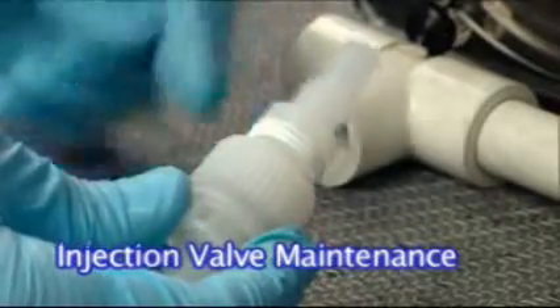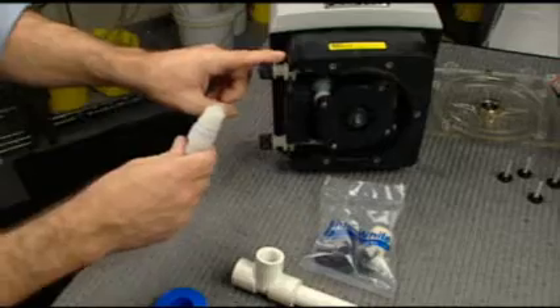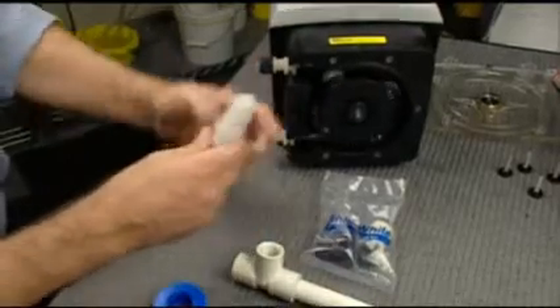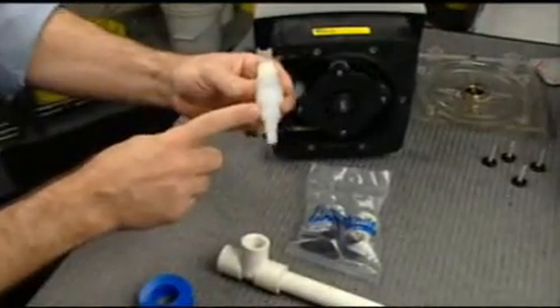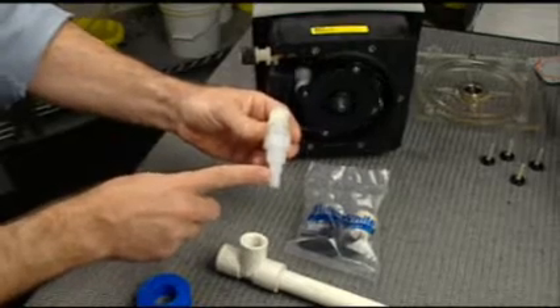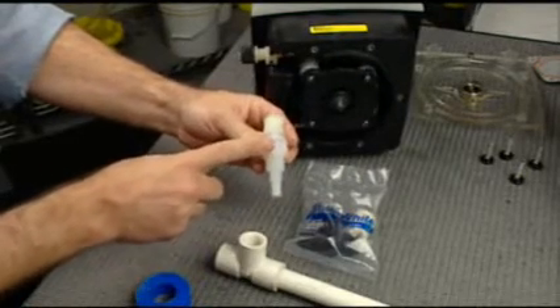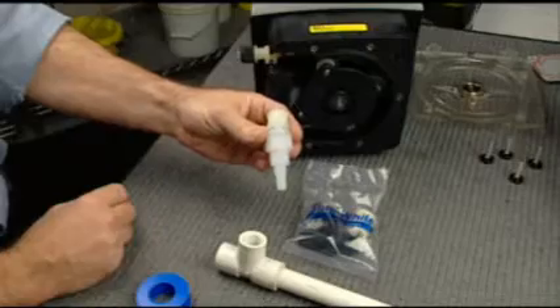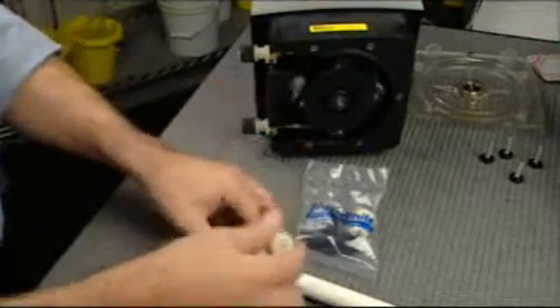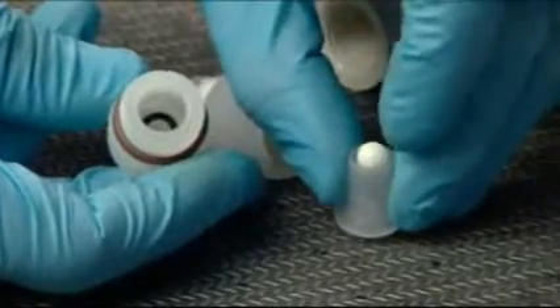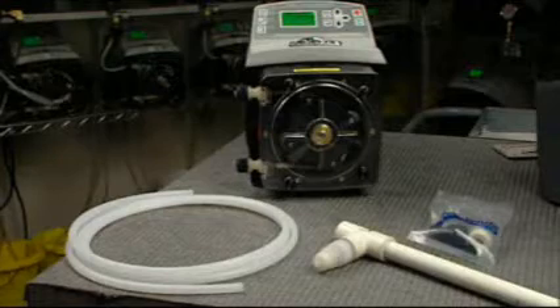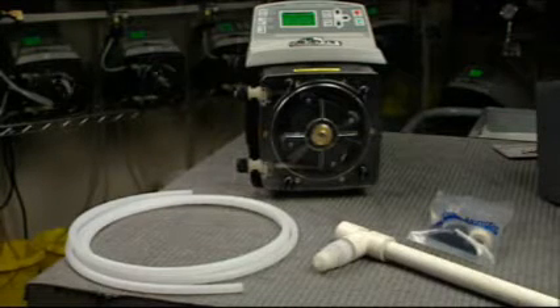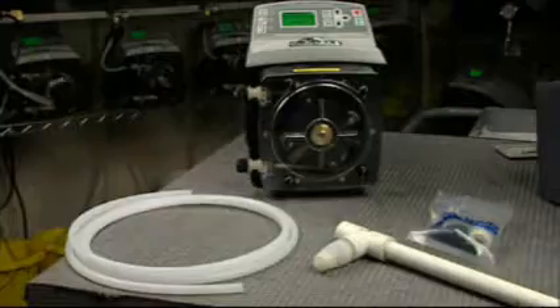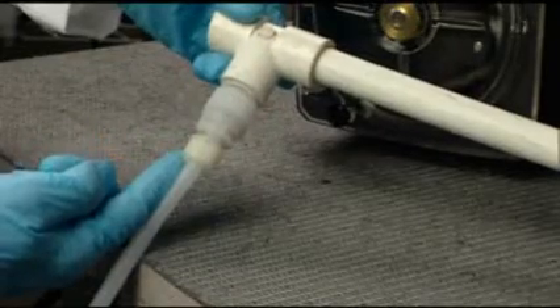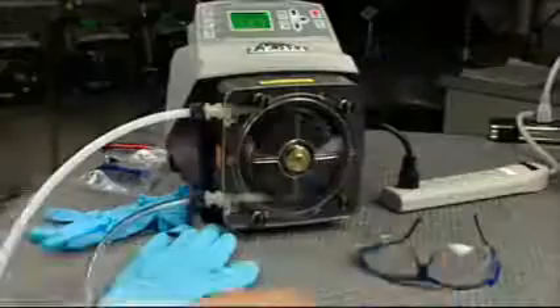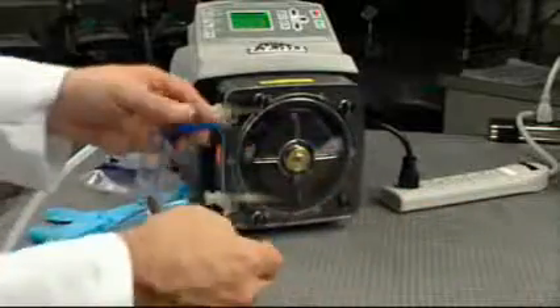The injection valve is used to provide a connection from the outlet tubing of the pump to the piping system. It includes both 1/2 inch and 1/4 inch male pipe threads and an internal check valve to prevent backflow during pump maintenance. The injection fitting check valve should be inspected periodically and replaced if worn or not working properly. If clogged, the fitting can be disassembled and cleaned. If possible, install the valve in an upward position to prevent gases from becoming trapped in the valve.